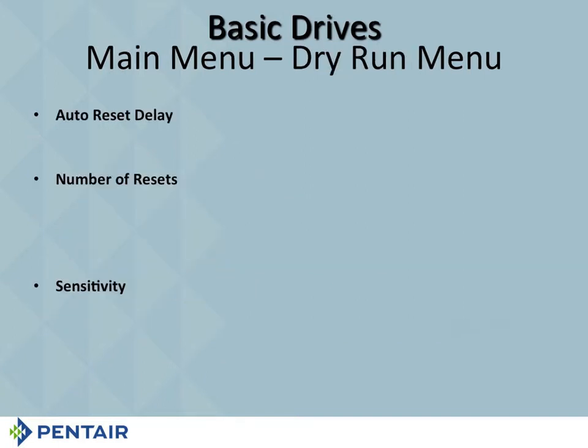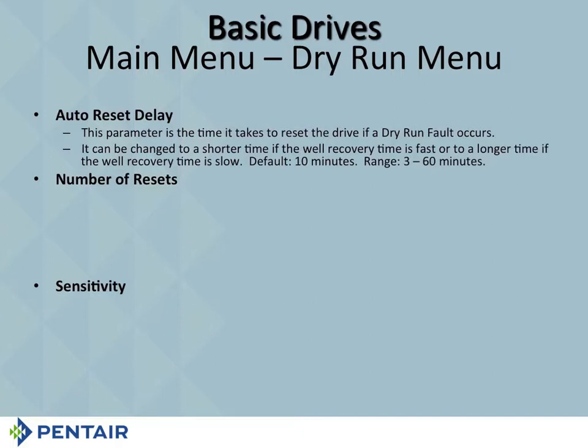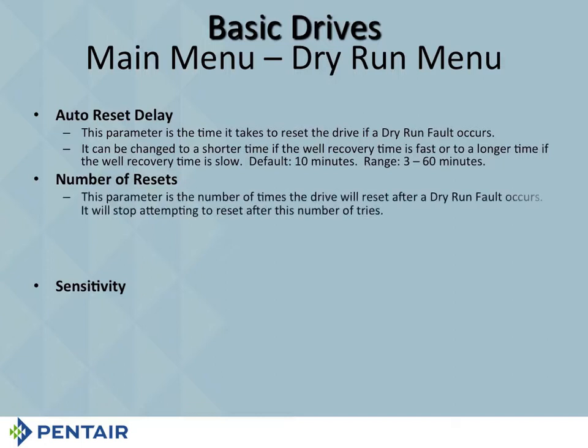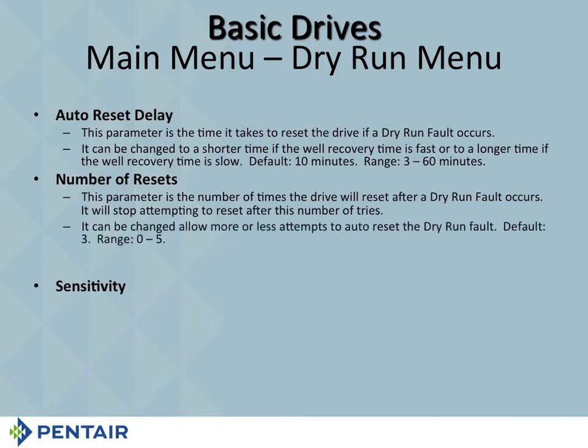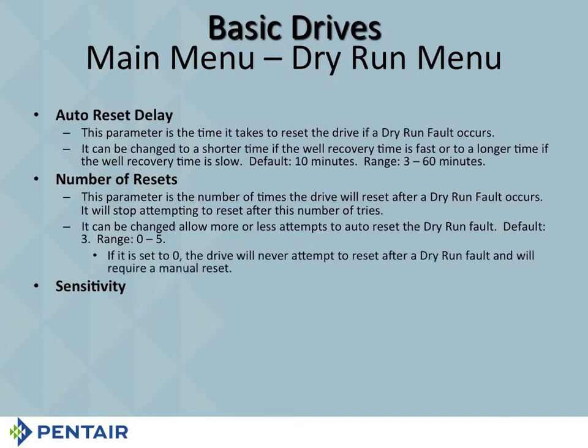Under the main menu for dry run, remember the auto reset delay. We say wait 10 minutes. It can go down to 3 or up to 60. Remember, if your customer's in the shower, you put 60 minutes. They're waiting 60 minutes to get water to rinse off with. The number of resets, we set it for 3. The range is 0 to 5. All right. If you set it for 0, remember the drive never attempts to start again. Somebody has to go down and push the reset button.